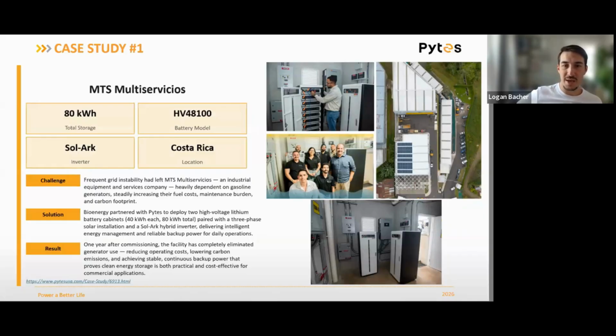You have the BMS inside the batteries directly communicating with the inverter. In other words, you program the inverter when to discharge the batteries and how hard or how fast. But at the end of the day, it's the BMS that provides those limitations to the inverter. So the question of how the batteries charge and discharge with the inverter is all controlled by the BMS. You input settings on your inverter to match your application, but at the end of the day, it's the batteries that are in the driver's seat, if you will.